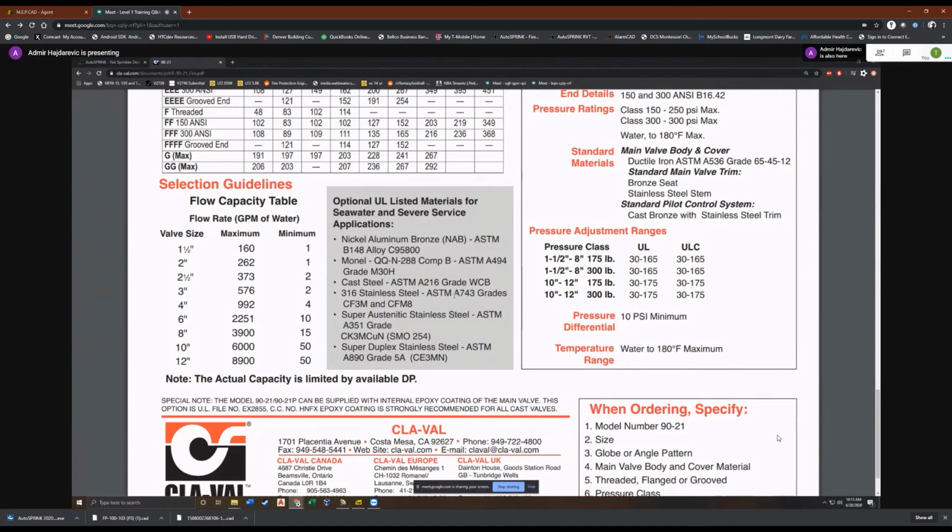But in this case I only have 500. Never say never, but unless my dry valves are using up a lot of water, which they won't be. These are basically garage areas. I just want to simplify it as much as possible. In our old program, we would just run the calc and design it to 150 psi max. We wouldn't get close to it, but we wouldn't go through all this extra work just to come to the same answer.